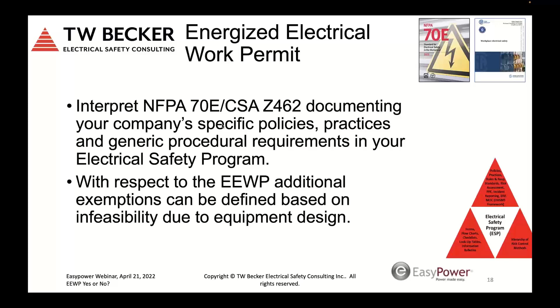I don't want repair or alteration performed in an energized state, but I want diagnostics, troubleshooting, inspections, and other work completed without a bureaucratic process requiring signatures on an energized electrical work permit. So I'm presenting these additional exemptions to be documented in an employer's electrical safety program, and they accept that. Their electrical safety committee votes and agrees, because why do we need a permit for these work tasks?